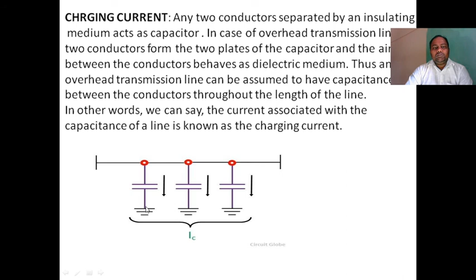So in a long distance transmission line during a lightly loaded condition, the receiving end voltage will be higher than the sending end voltage. We already discussed that, it is the Ferranti effect. This is because of the charging current and capacitance effect of the line. It is called the Ferranti effect. So the cause of the Ferranti effect is the charging current.